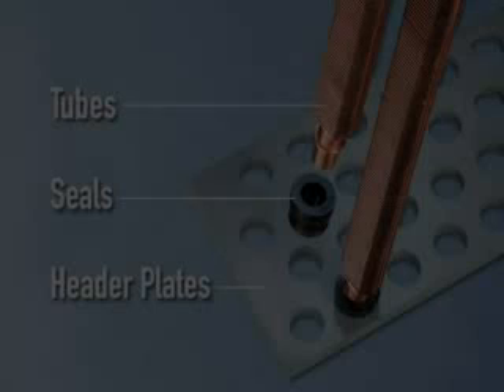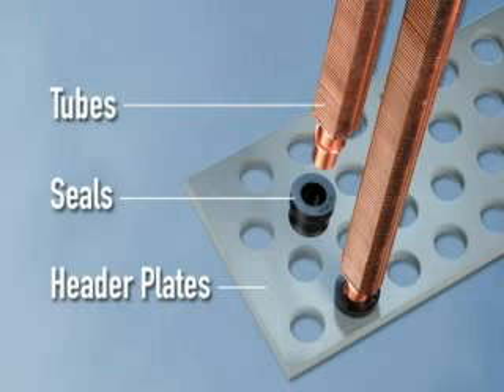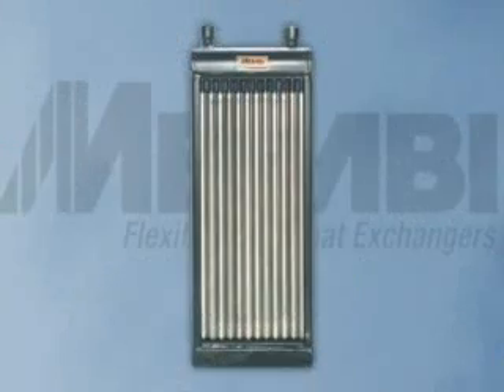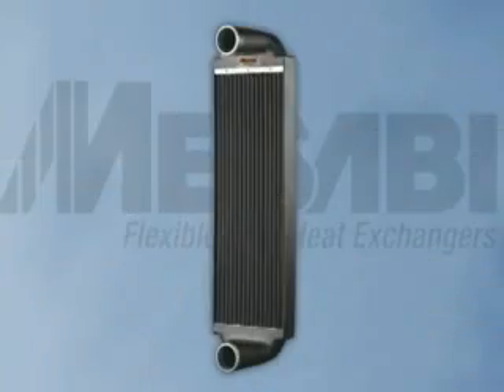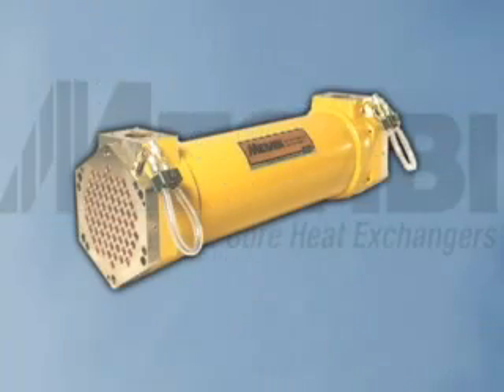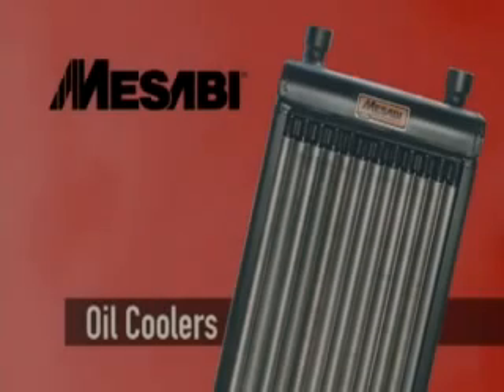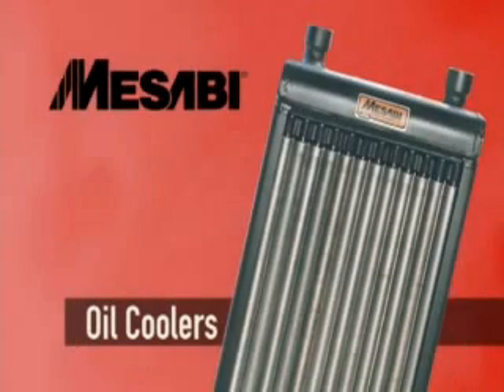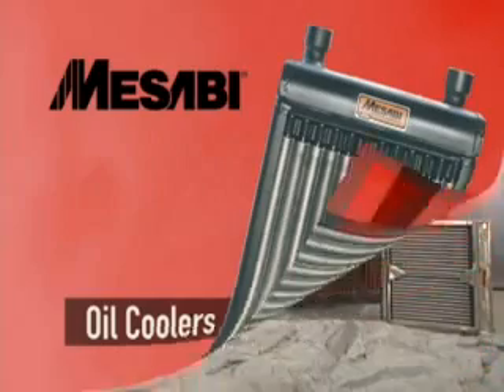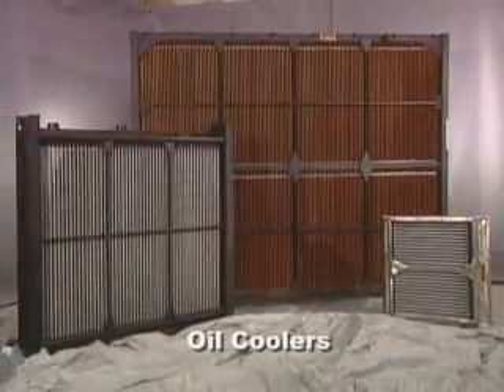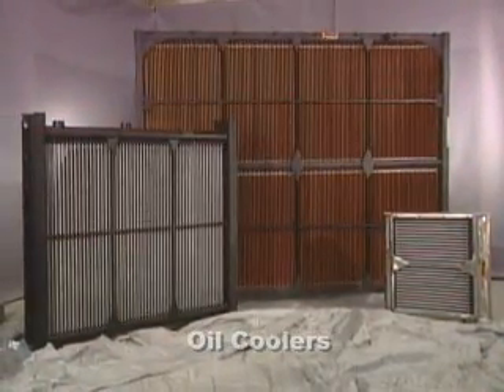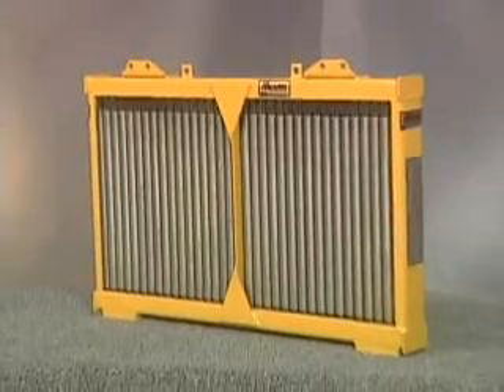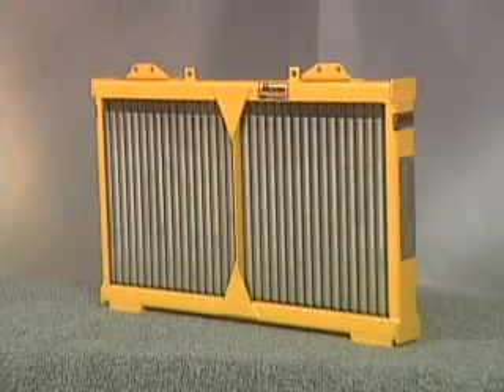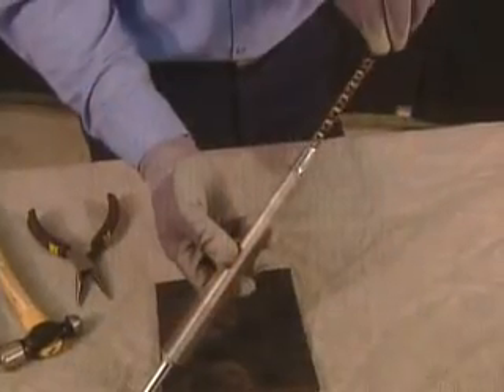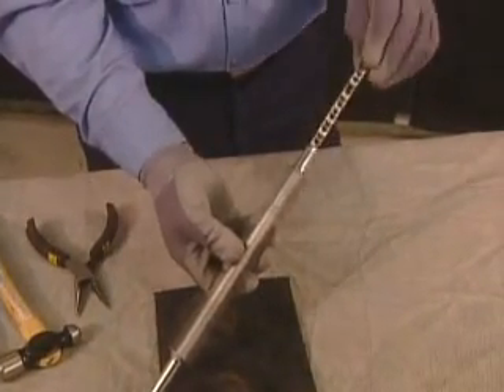L&M Radiator has applied the replaceable tube concept to heat exchangers other than engine radiators. These products include oil coolers, charge air coolers, and tube and shell coolers. L&M has a family of oil coolers for almost any oil-to-air cooling. The standard Mesabi oil cooler has lightweight aluminum cooling tubes with integral circular finning rolled from the tube wall.